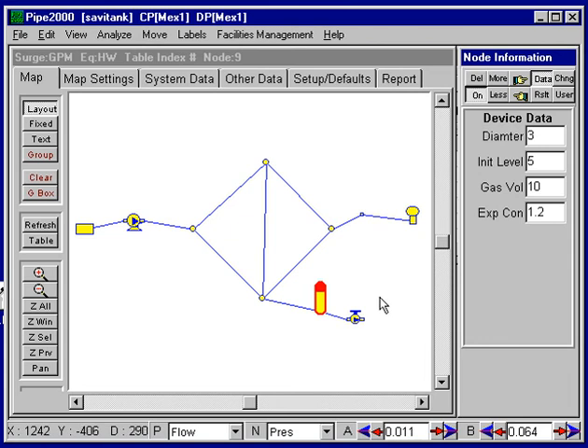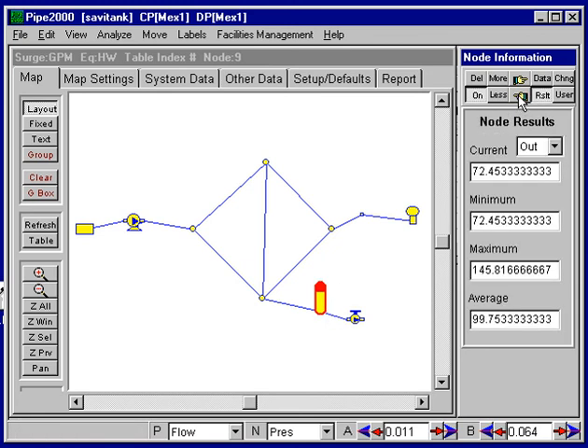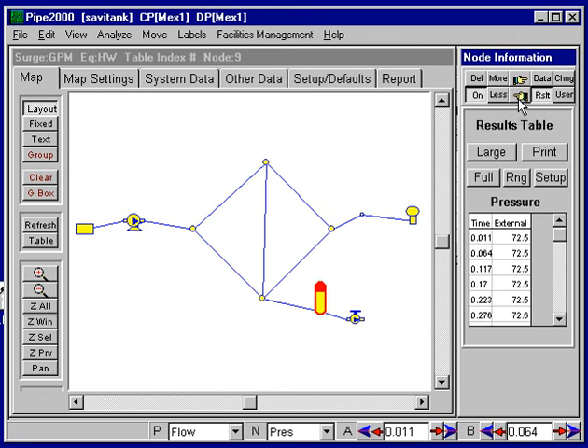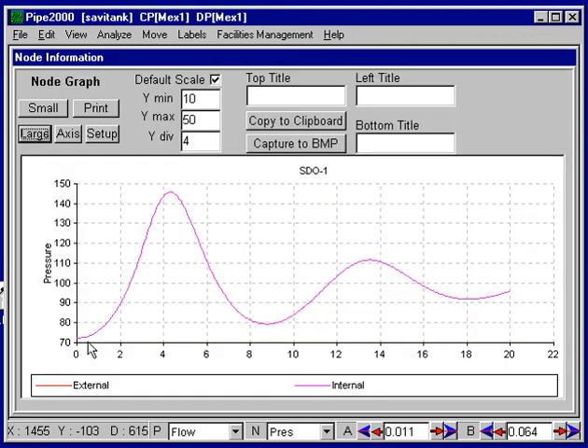Now we've added this element and the data, so we can run the analysis. We've already run the analysis, so we can illustrate what the results look like. Turning on results and selecting this node, we get a pressure plot at the surge tank. The pressure starts at around 70, surges up to a little over 145, and then levels out at about 90.